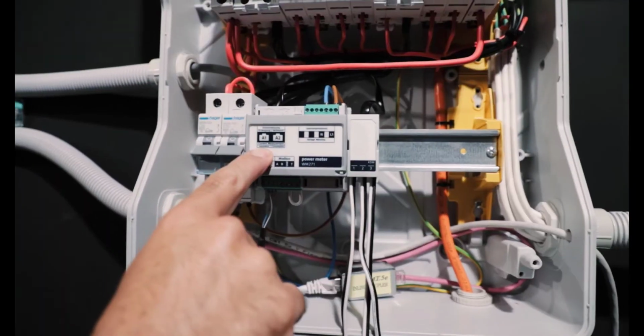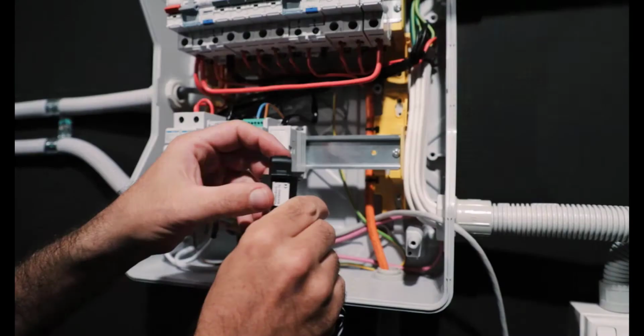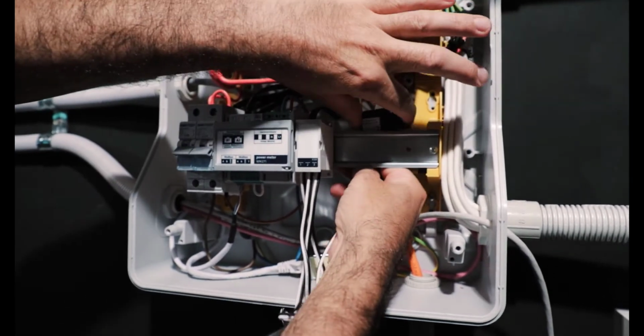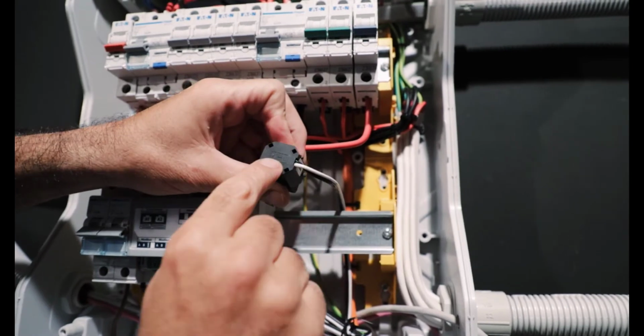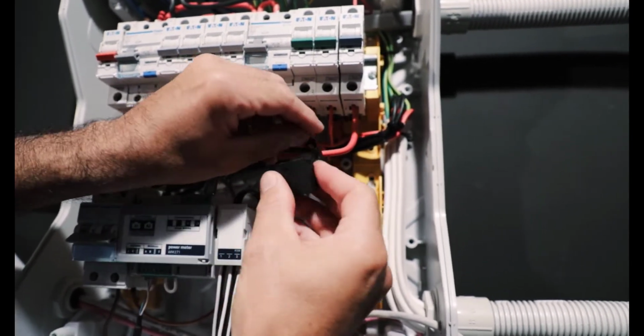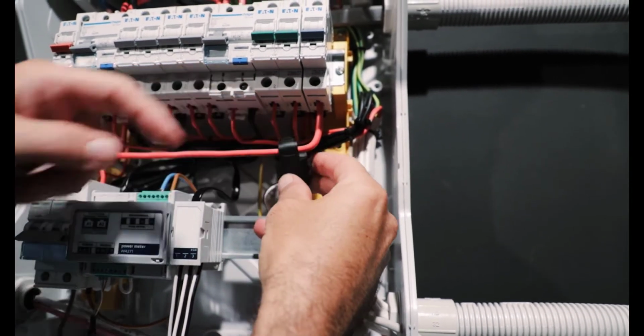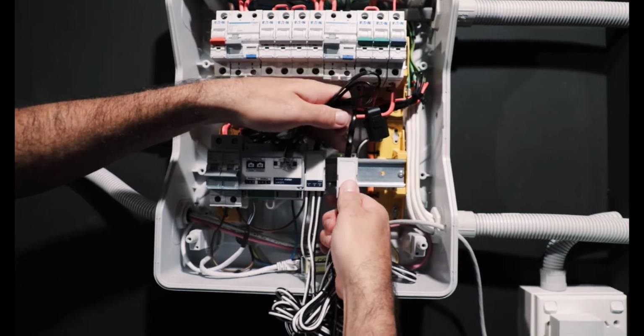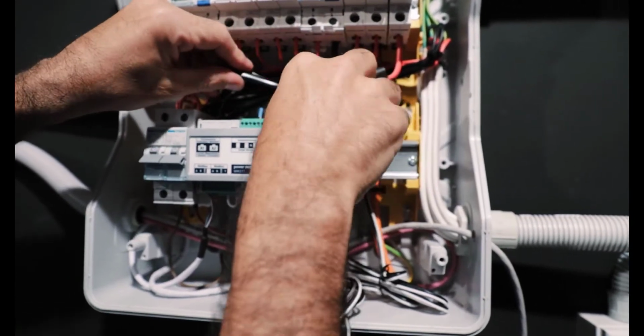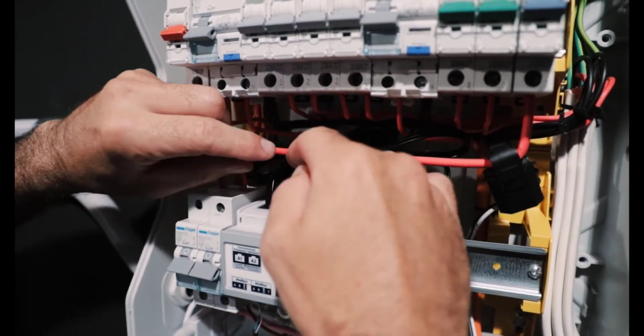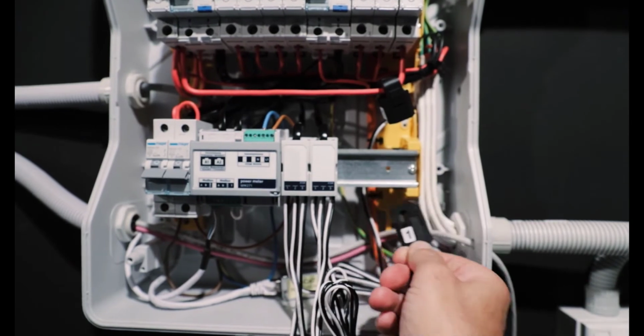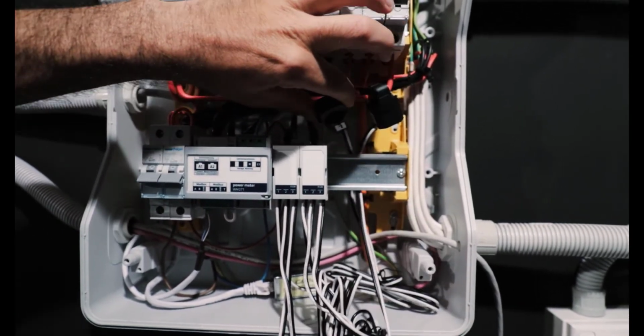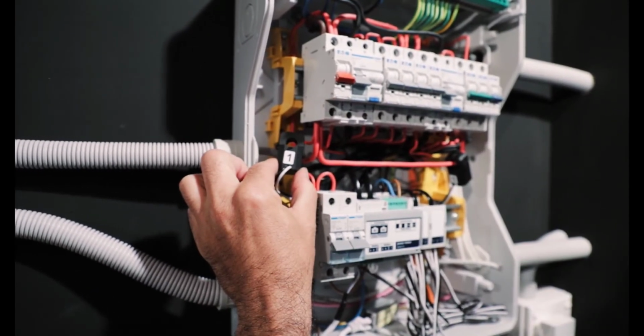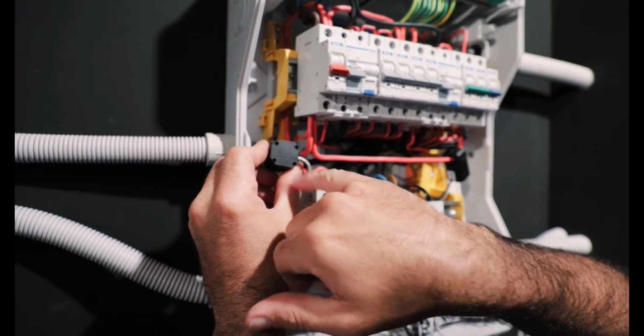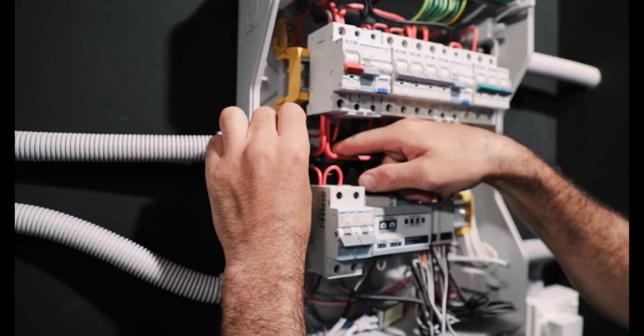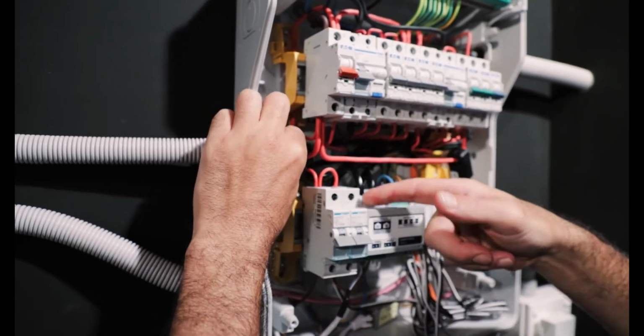First thing for generation. And generation, very simply, just goes straight onto that connection there, coming out from the AC isolator from the PV system, which connects through to the main MCB, or main grid supply isolator. And then we plug in the CT set, the transducer for consumption. Takes CT number 1. Then we take it onto the separated supply, which is just feeding the load circuits. So all the CT is looking at is the actual consumption itself.